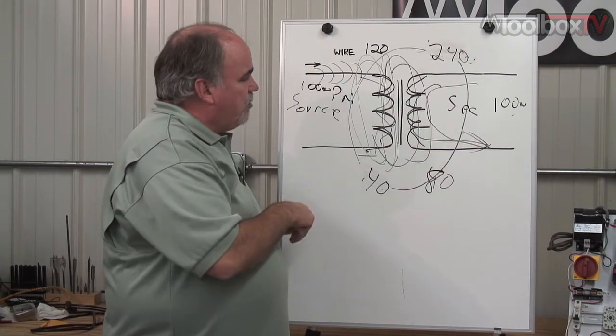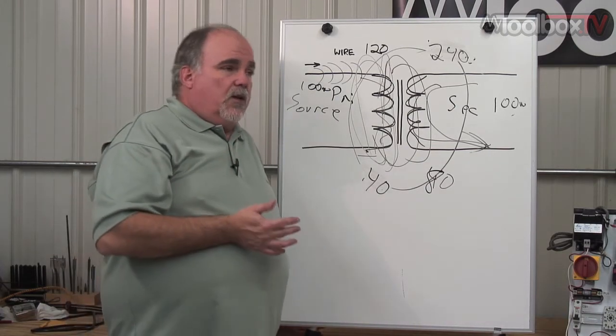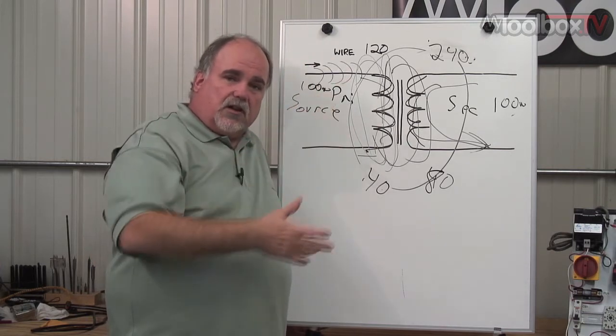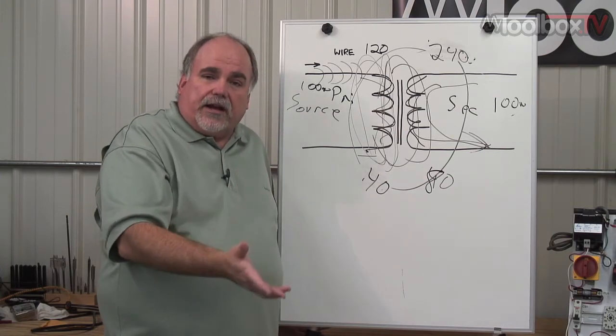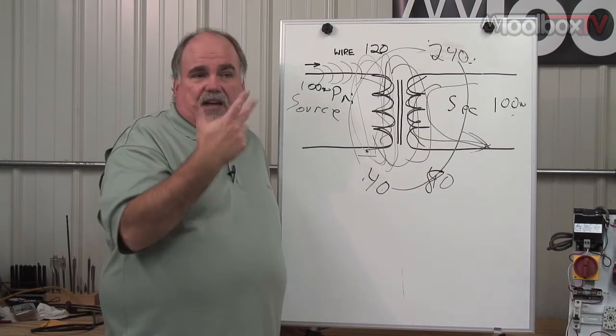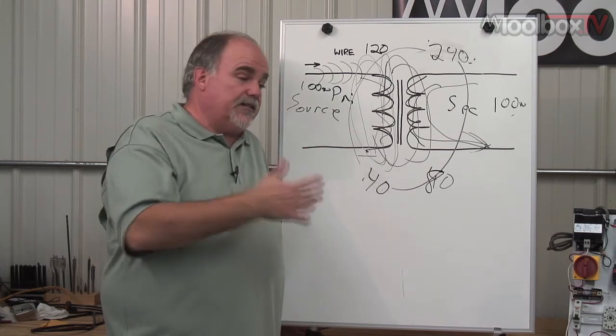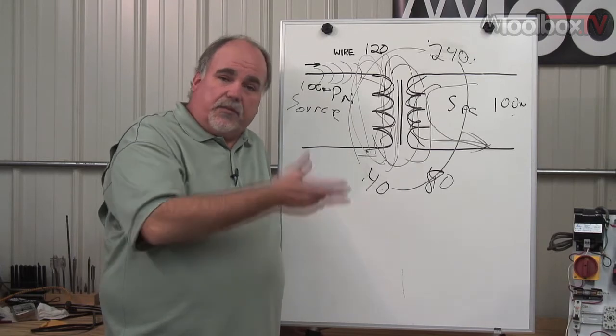This is the reason that we have power lines with extremely high voltages. If you've been out in the country and seen miles and miles of long high voltage power lines, the situation there is the power plants create generally AC current in the neighborhood of 24,000 volts. Right outside the generating station, they step it up in the yard. It could be up to 345,000, 500,000 volts is a common one.